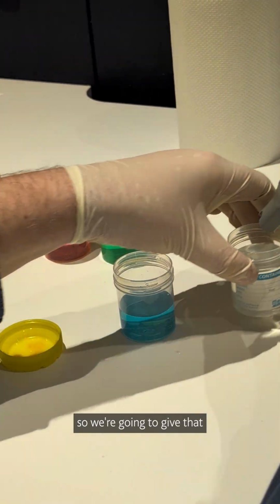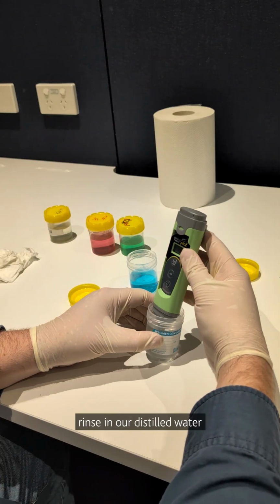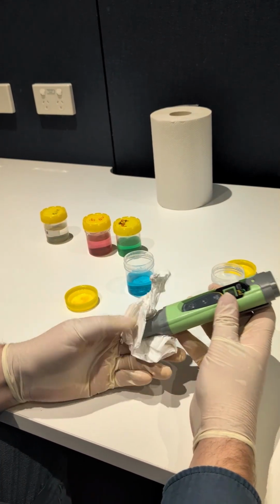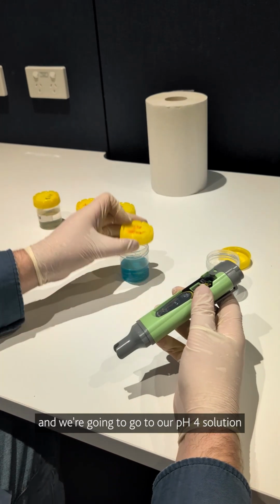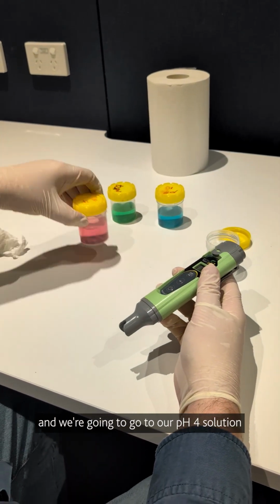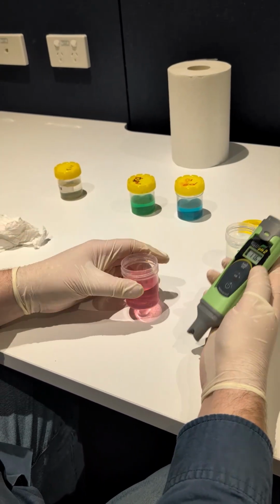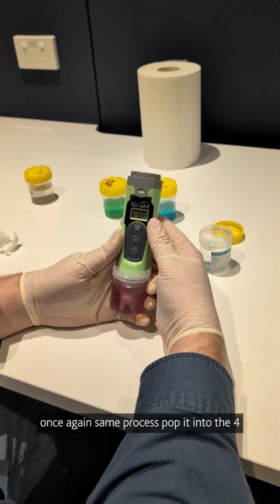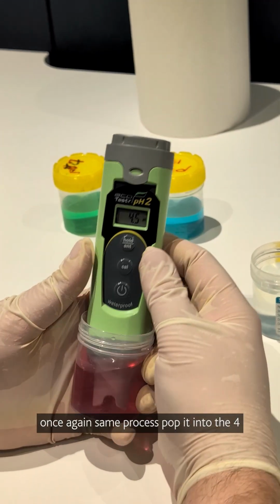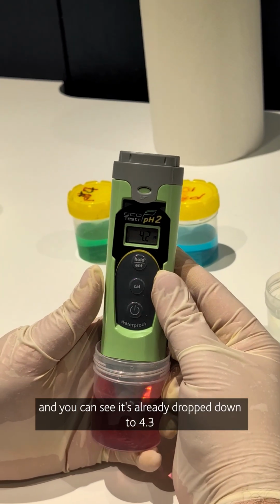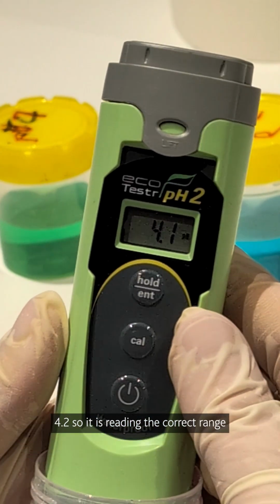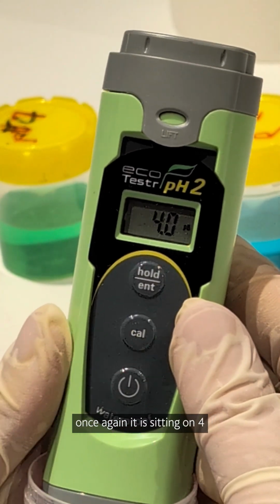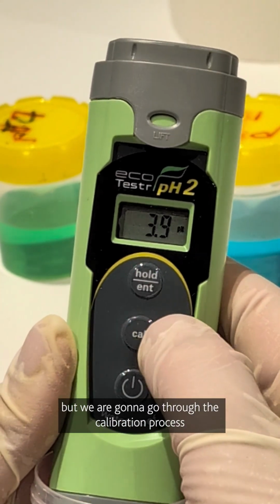So we're going to give that a rinse in distilled water, dry off our probe with some paper towel, and we're going to go to our pH 4 solution. Once again, same process. Pop it into the 4, and you can see it's already dropped down to 4.3, 4.2, so it is reading in the correct range. Once again, it is sitting on 4, but we are going to go through the calibration process.